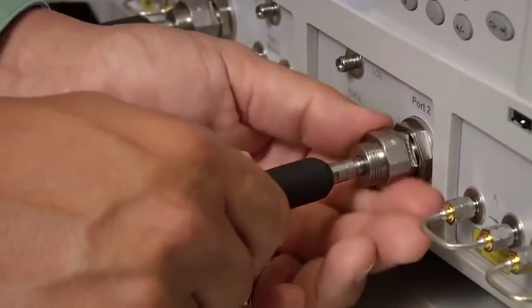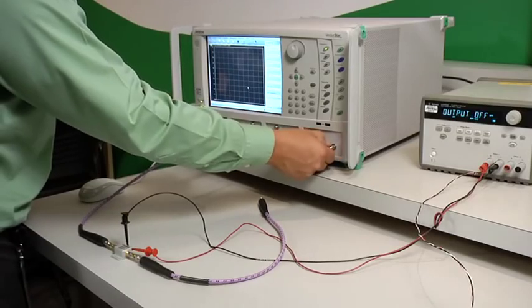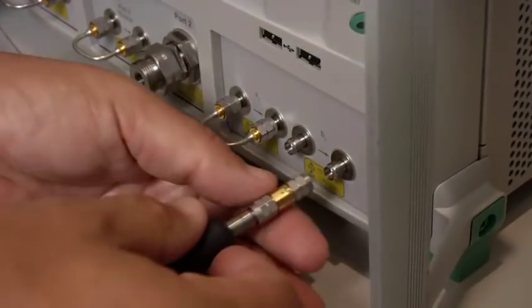It is recommended that the noise figure measurements are made by connecting directly to the VNA receiver. For VectorStar, that's port B2. This allows you to get optimal performance from the composite receiver.